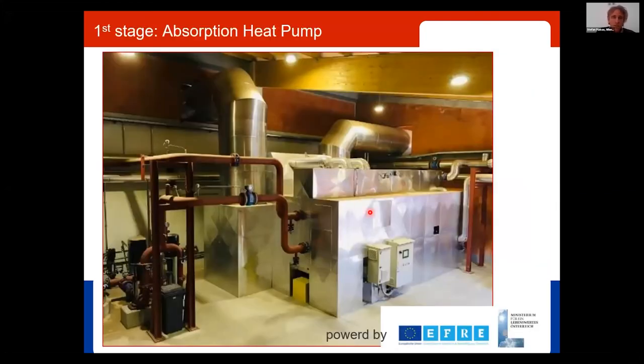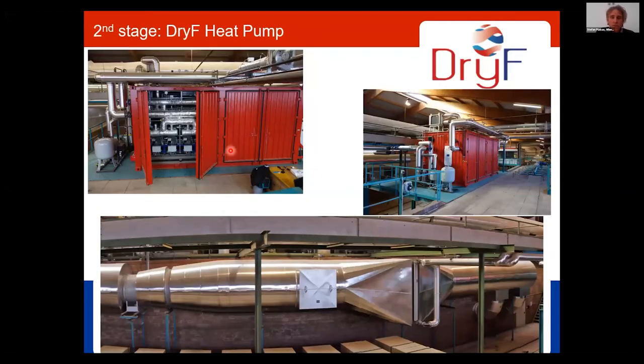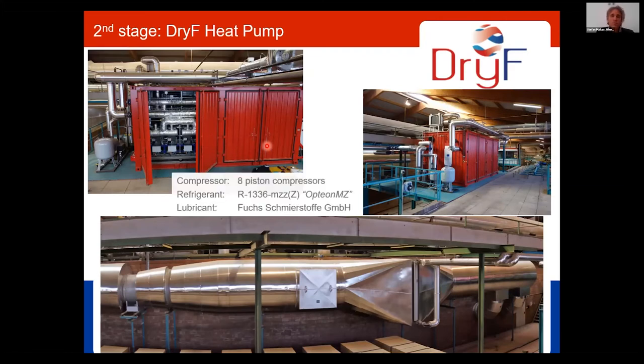How does the installation look like? This is the absorption heat pump. It is hidden behind sheet metal here. And this is the dry efficiency heat pump in a container. Inside we find piston compressors, 8 piston compressors. The refrigerant is developed by Chemours, the lubricant by Fuchs Schmierstoffe, the other partner in the project. Below here you see this recirculation duct with the big heat exchanger. Yeah, this is the installation.